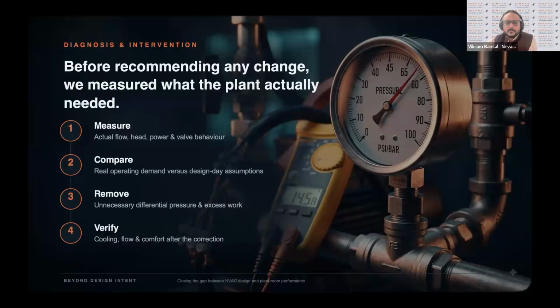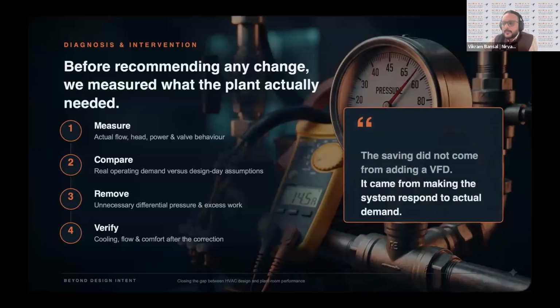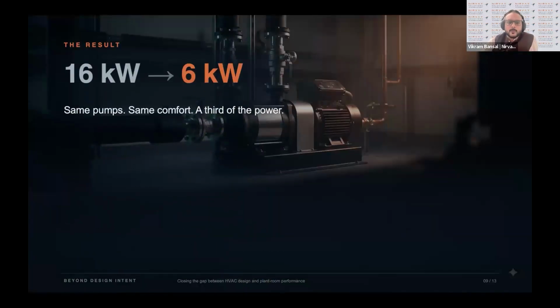The saving did not come just from putting in a VFD. It came when we started making the system respond to the actual demand. And the result was that the same 16 kilowatt went down to 6 kilowatt. The same pumps, the comfort was the same.